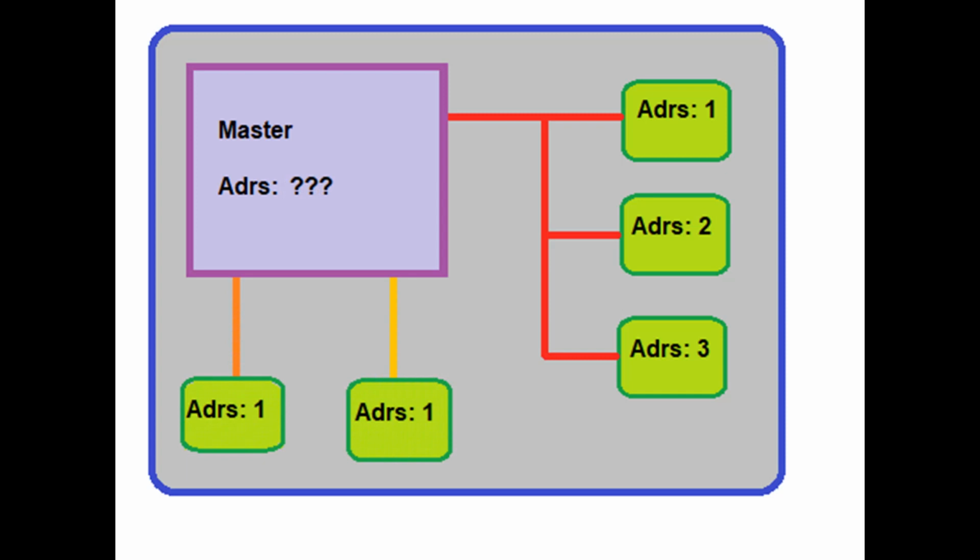Addresses for devices on different serial lines, or devices operating with network connections, need not be unique, since a message sent to one outstation cannot accidentally be detected by another. Likewise, a master address, except on a serial line with 2 masters, if such a topology even exists, is not really important.